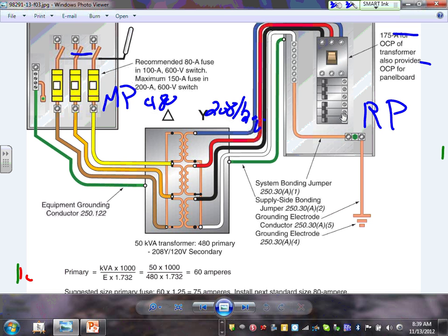On the primary side, since we're using a fuse and since based on 250, you take 1.25 times the full load current on the primary, size the fuse, and on the secondary 1.25 you size the circuit breaker, and off it goes. Again, I will be using this same example, a couple of examples, guys, in the industrial project.